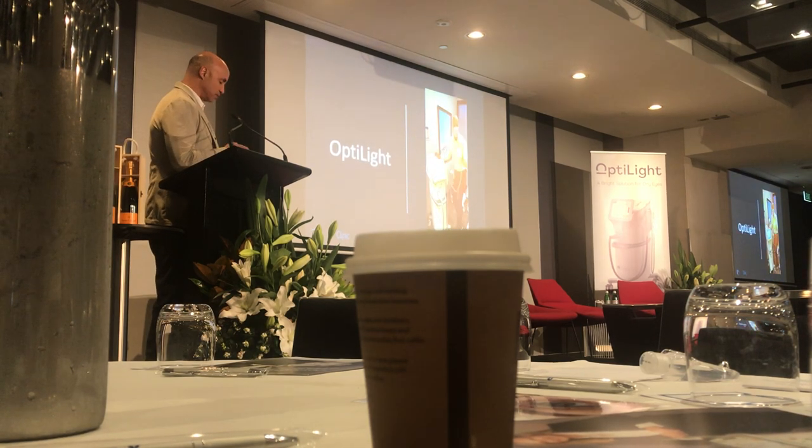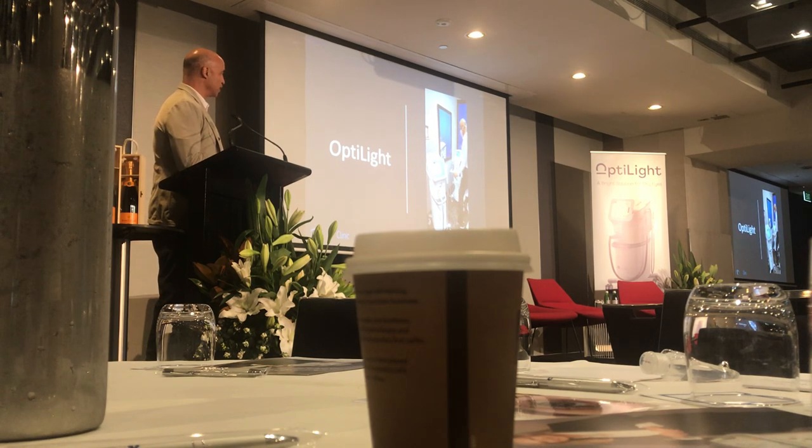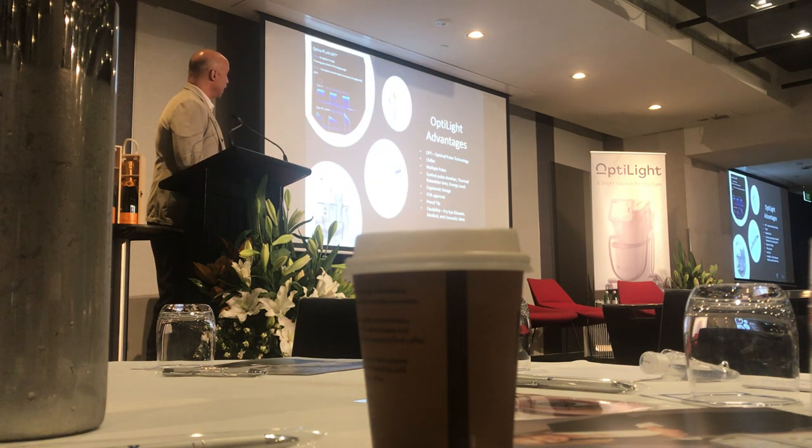Going from M22 to OptiLight — it has all the same advantages: the larger footprint with the chiller, multiple pulses, even energy distribution. If you put in 10 joules, it's going to give you 10 joules — there's no decrease of energy as you use it over time.